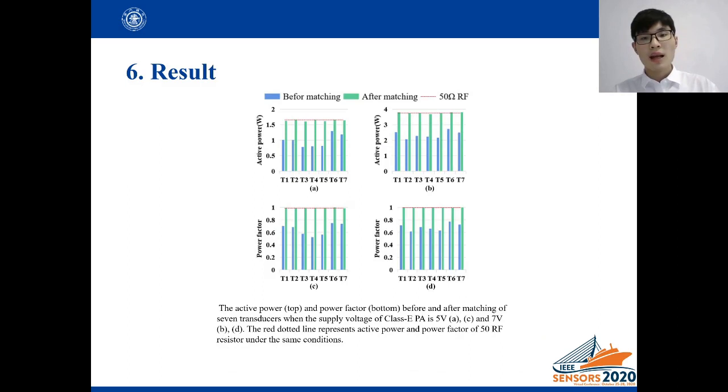This slide shows the comparison before and after matching under the class E power amplifier. The mean active powers of the 7 transducers have been increased by 66% and 59%, high percentage, and the mean power factors have been increased by 53% and 46% with a dynamic impedance matching network under the conditions of 2 supply voltages of class E power amplifier.